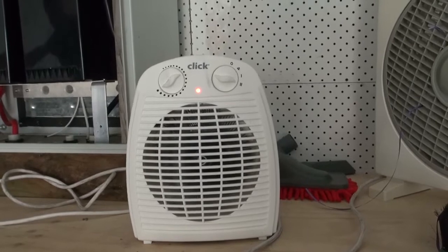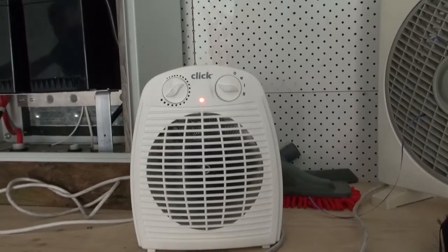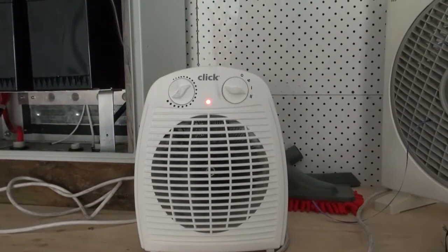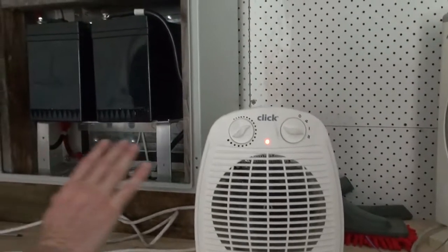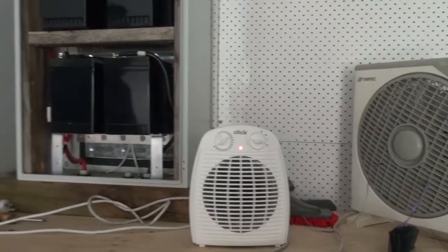As you can see, there's no interruption to the actual load. Turn this back on again, the power has resumed. So it flickers for one cycle, which is the normal changeover. But the load itself is fine. And there we go. So thank you very much, and stay tuned for more details.